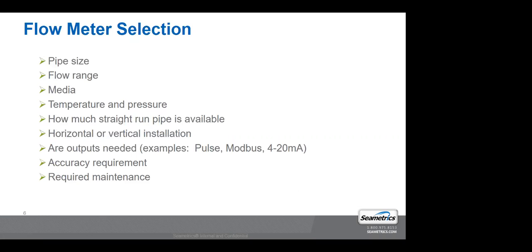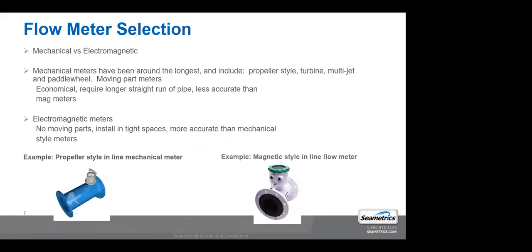What's the accuracy requirement? That's kind of a critical one to know, because as you're looking at what type of technology you're going to select, a lot of times when you're looking at price points on flow meters, the less accurate the meter, usually the less upfront costs it's going to be. Doesn't mean your overall cost of ownership is going to be less, but your upfront out-of-pocket costs could be less. And when we look at overall cost of ownership, what's the required maintenance on that type of technology that you've selected?